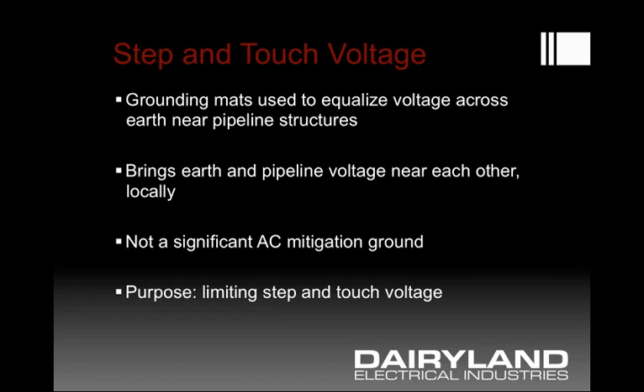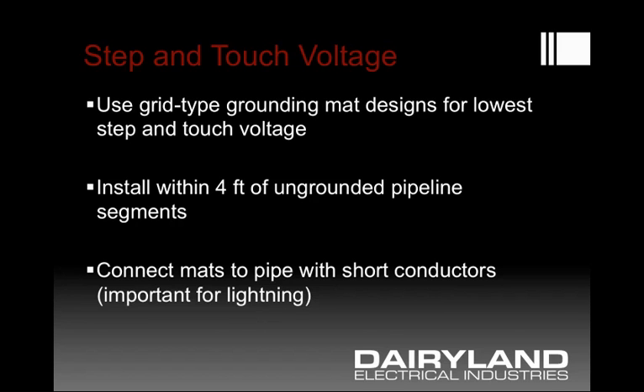We just need to keep the pipe and the local earth at a limited voltage relative to each other to protect workers. When it comes to grounding mat design, a grid-type grounding mat is going to have the lowest resulting step and touch voltage. Out to a distance that anyone could reach and still touch a pipe — basically about four feet — you'd want grounding mats installed around piping segments at a valve site or within a station.